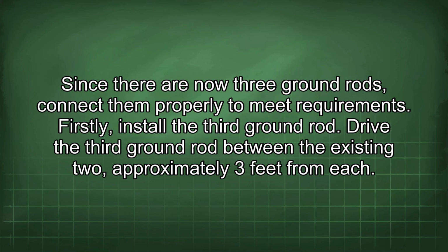Since there are now 3 ground rods, connect them properly to meet requirements. Firstly, install the 3rd ground rod. Drive the 3rd ground rod between the existing 2, approximately 3 feet from each.